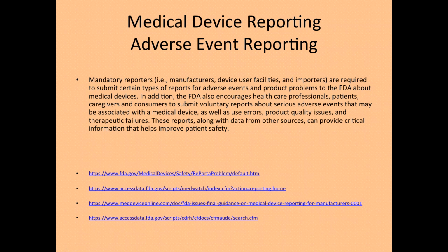that if your product is involved in any adverse effect, you have to report that to the FDA. I'm going to give you an example. You've got a patient in the operating room, and let's say it's a patient warming blanket to keep the patient warm, and the patient dies on the table. You know about it. You've got to file an FDA MDR and do an examination and an evaluation of whether your product contributed to the death on the table. Any serious adverse event may be associated with the medical device, any user errors, product quality issues, and therapeutic failures.